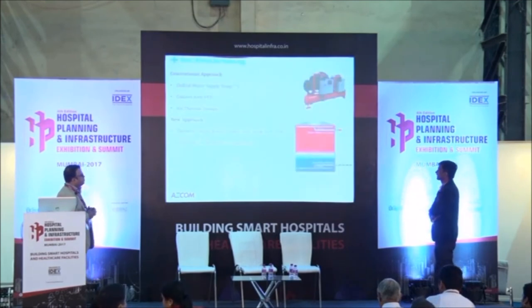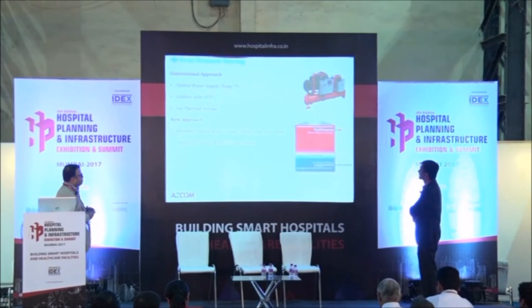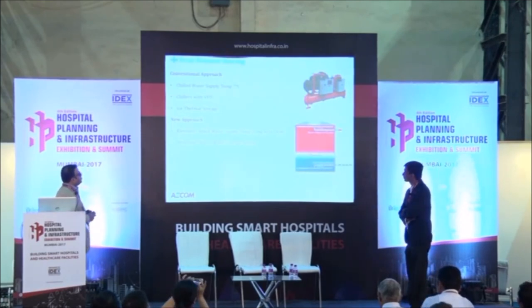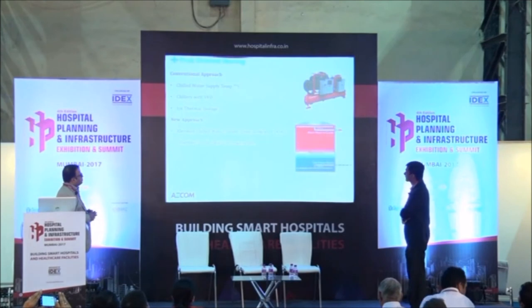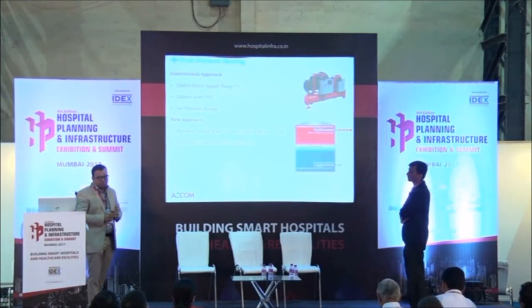The conventional approach for chillers uses 7-degree centigrade water with VFDs and ice thermal storage — ice thermal storage being for chopping the peak load. There are better ways now: elevated chilled water temperature as seen with DOAS and radiant cooling systems, and instead of ice thermal storage, stratified chilled water storage tanks.